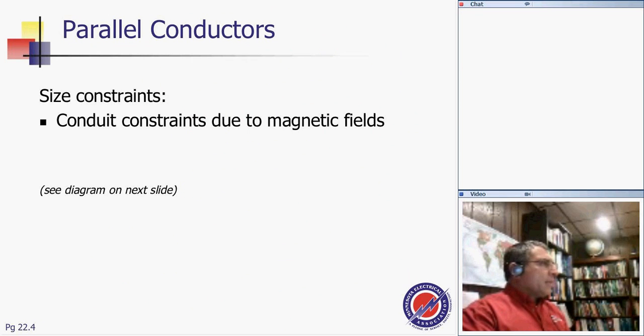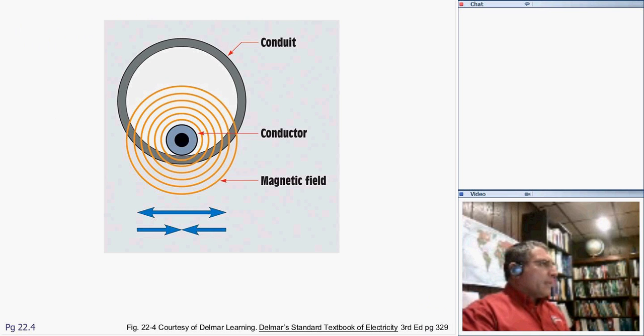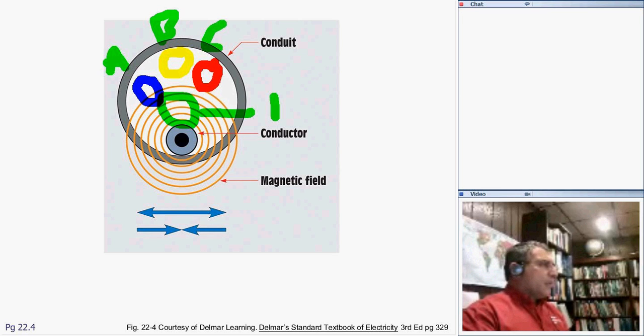We parallel conductors, guys, due to magnetic fields. What we do, you see here. With parallel conductors, you're supposed to put all the conductors of the same circuit in the same conduit. So I have here my phase A, here's phase B, and here's my phase C, neutral, and neutral. If you put the phase A, phase B, phase C, and a neutral in the same conduit, what happens is you reduce the magnetic field, as the conductors cancel each other. In short, you end up with lower impedance and less heat. Lower impedance, less heat.